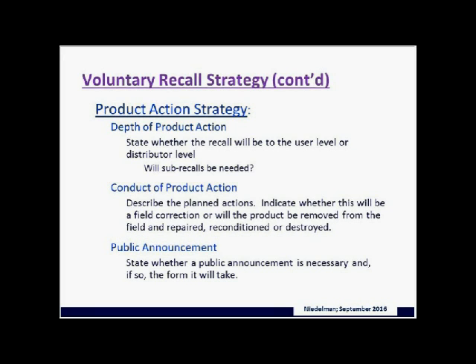You need to describe the planned actions, whether this is a field correction, whether the product will be removed. Are you asking people to destroy it in the field? Will you repair it in the field? Will it be reconditioned perhaps as a non-medical device? Or will the product be destroyed? Or will it be fixed during the next preventive maintenance service? And sometimes that is the appropriate answer, depending upon what fix is needed. You just need to account for those devices that are not under preventive maintenance contracts, because those products still need to be repaired aside from those that do come in for preventive maintenance.